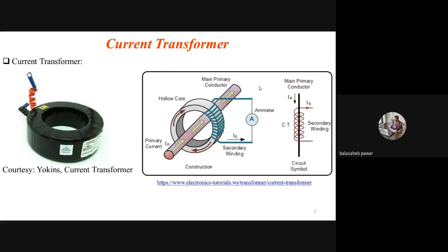So you have to remember this thing. What I explained: when primary current increases, flux also increases around that wire. That means the induced flux in the secondary wound on that bobbin also increases, so the flow of current in that secondary also increases. And that we call the secondary current, IS. See, the primary conductor current will depend on how much load is connected across that primary with respect to neutral, and accordingly the generated flux will differ.